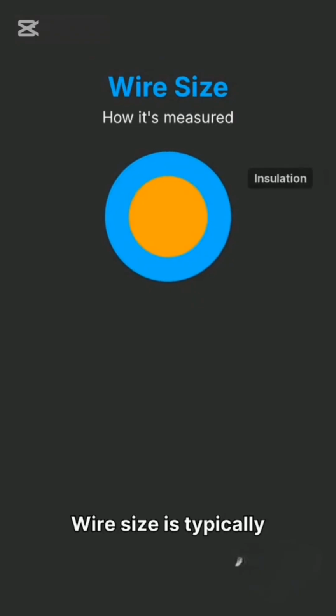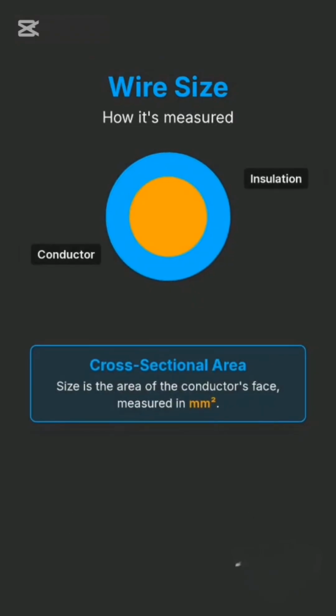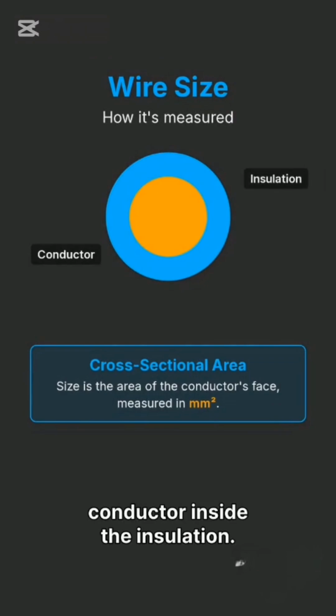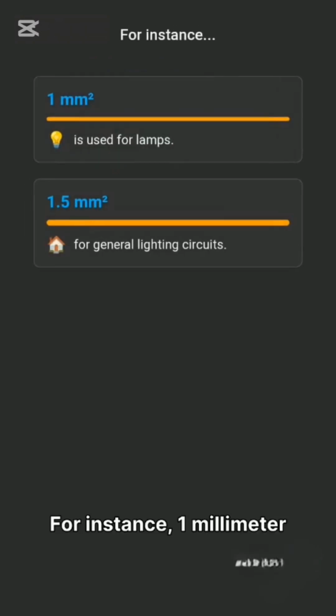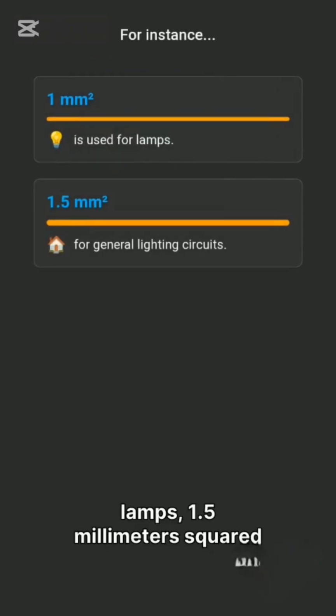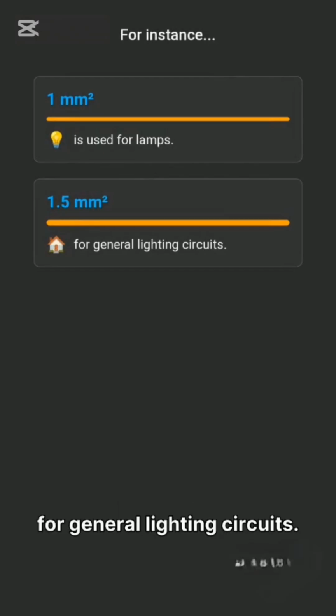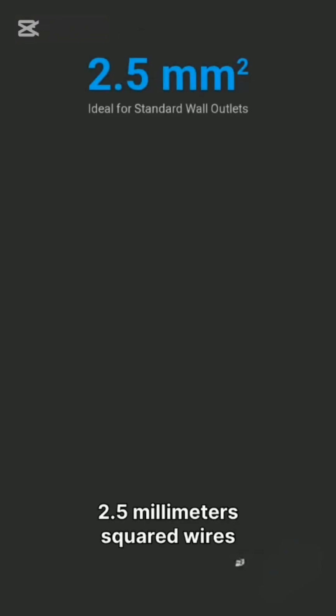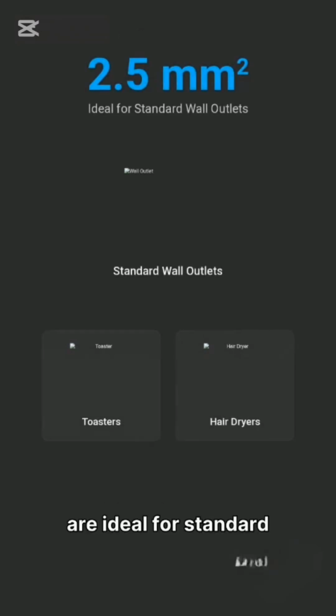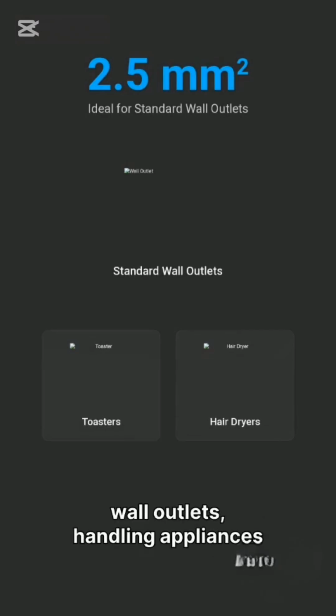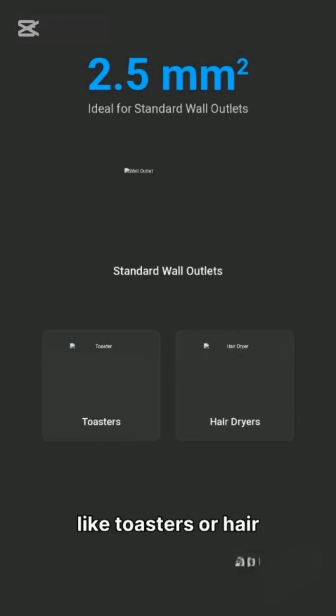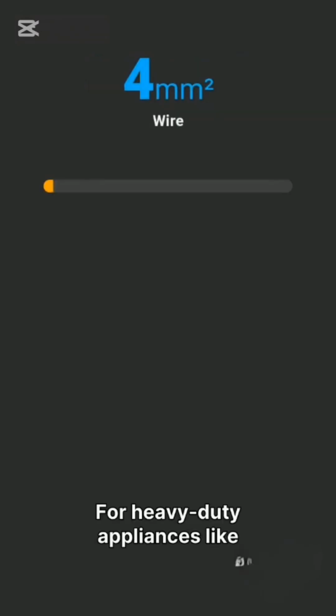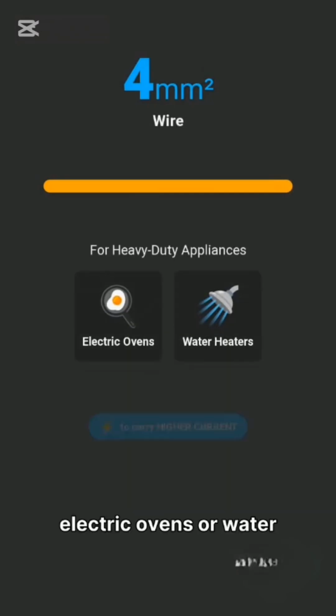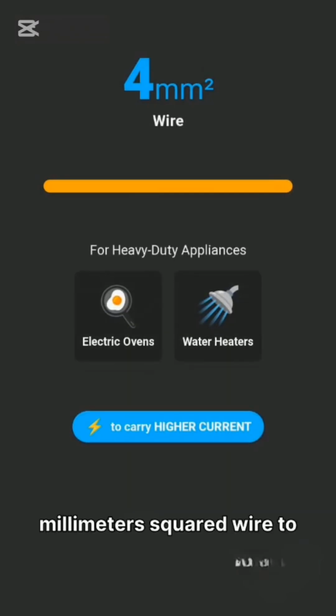Wire size is typically measured in millimeters squared, which refers to the cross-sectional area of the conductor inside the insulation. For instance, 1 millimeter squared is used for lamps, 1.5 millimeters squared for general lighting circuits. 2.5 millimeters squared wires are ideal for standard wall outlets, handling appliances like toasters or hair dryers. For heavy-duty appliances like electric ovens or water heaters, you'll need 4 millimeters squared wire to carry higher current.